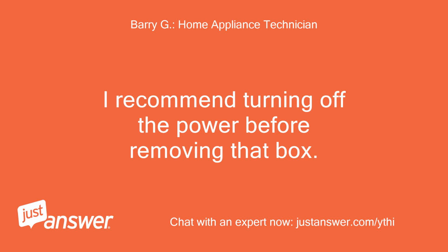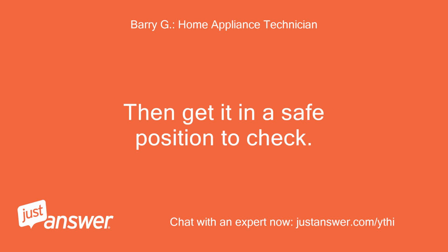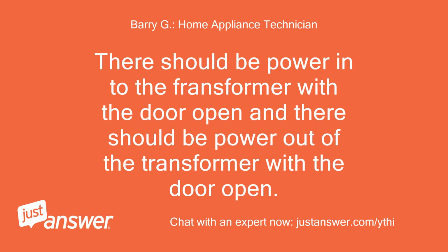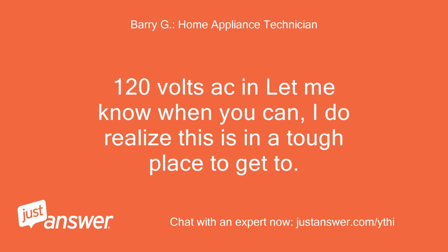I recommend turning off the power before removing that box. Then get it in a safe position to check. There should be power into the transformer with the door open, and there should be power out of the transformer with the door open, 120 volts AC. Let me know when you can. I do realize this is in a tough place to get to.